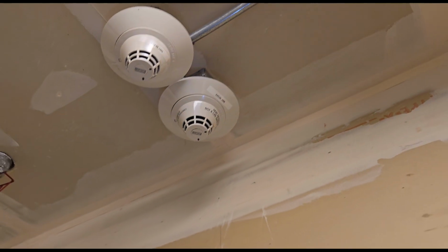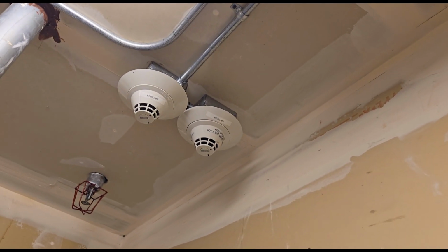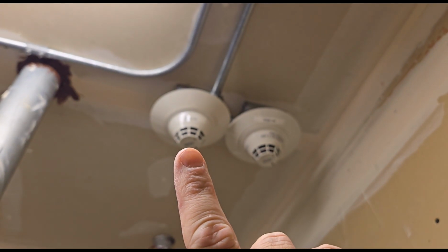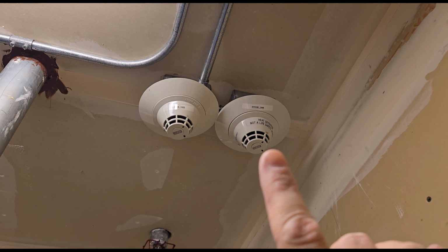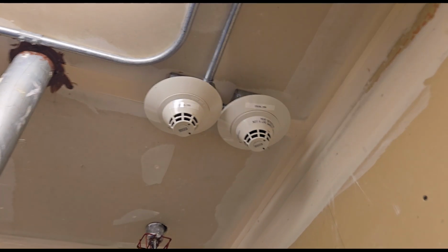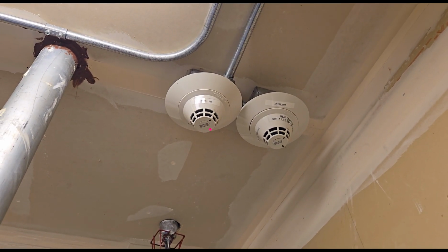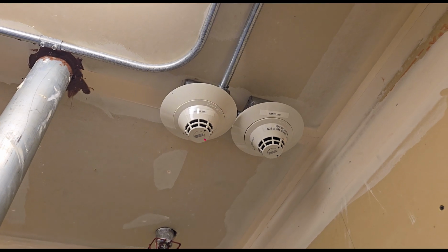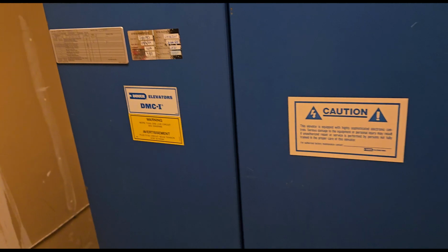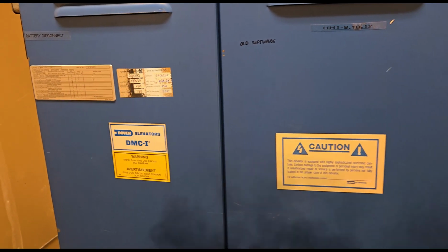Alright, turn red. I heard the machine click. So now we have our smoke active, so the elevator recalled, and we have our heat active, so the power is lost. So now we need to go to the fire panel, reset it, because I'll have 2 alarms. Then I need to reset the breaker to turn the power on. And then finally, I need to reset the recall key to get the elevator back up and running. So let's go to the fire panel.